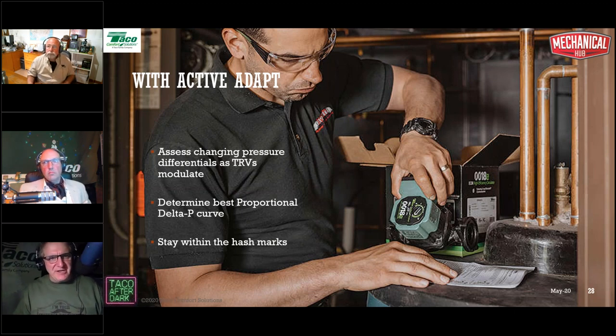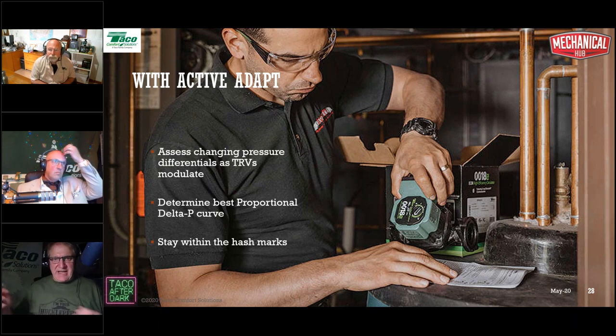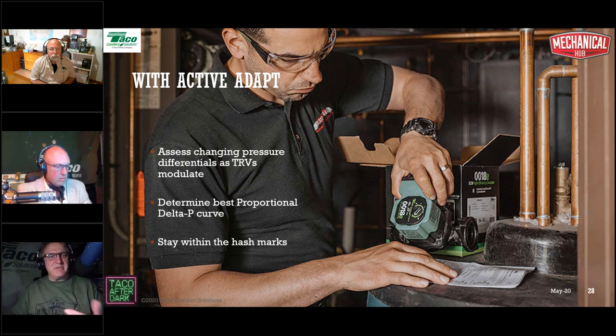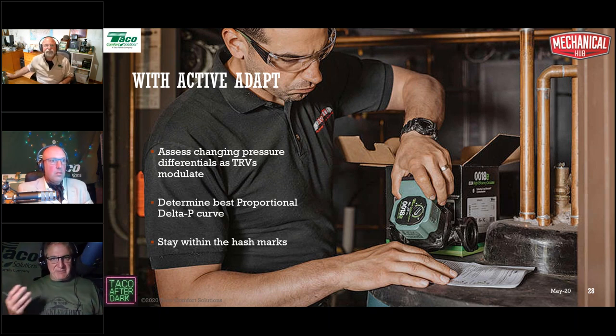What Active Adapt basically does is the pump needs to run for a while to figure stuff out. And then it will assess changing pressure differentials as those TRVs modulate. Over an extended period of time, it will determine the best proportional delta P curve for that system and will change as necessary. But it's not magic. It doesn't do a complete system assessment and then automatically change every time something happens so you always get the right thing. That's not how it works.